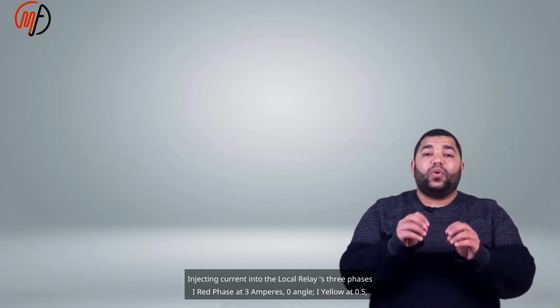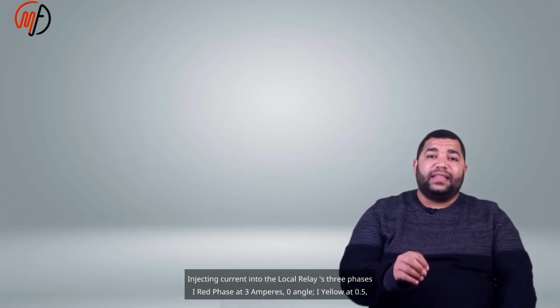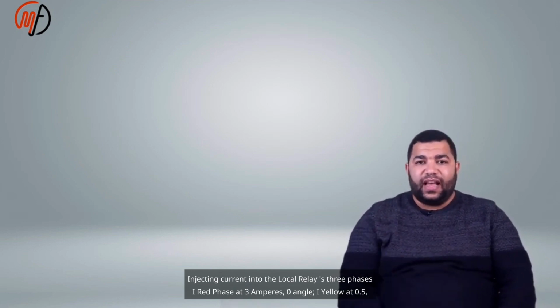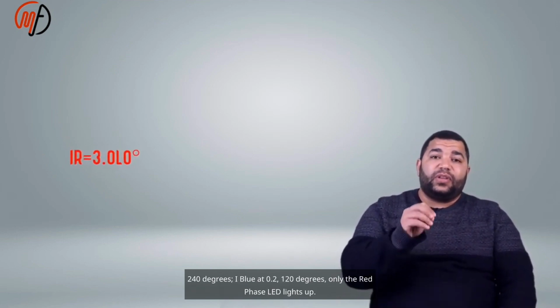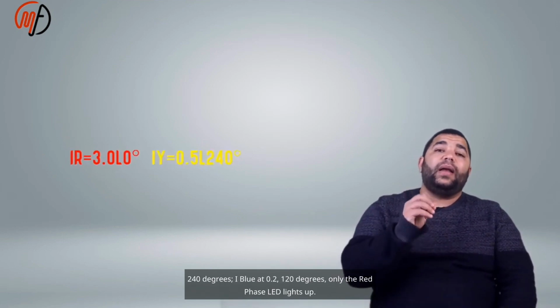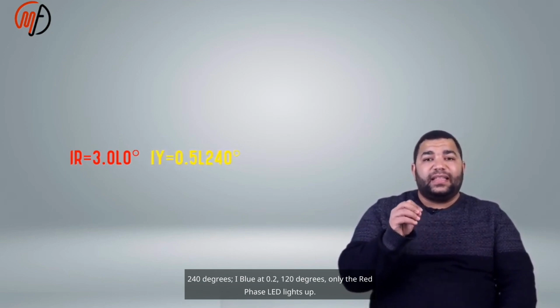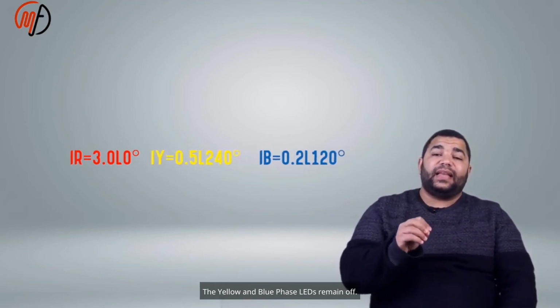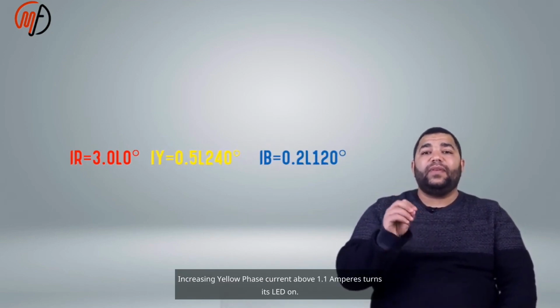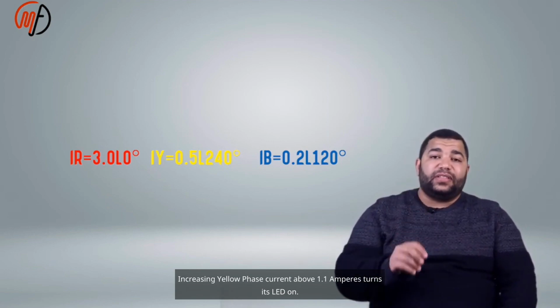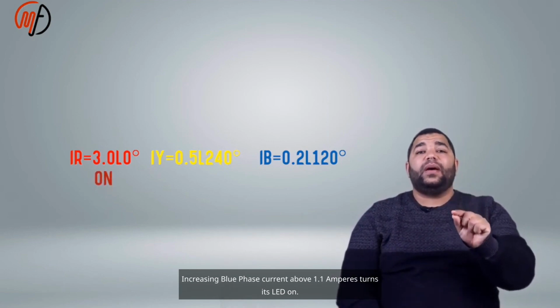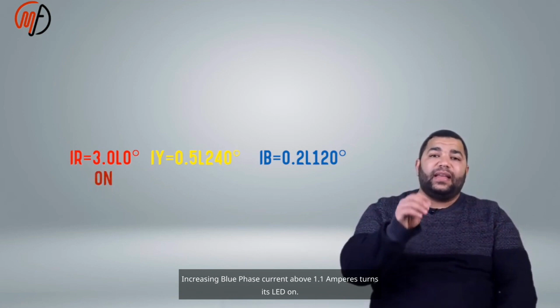Injecting current into the local relay's 3 phases: I red phase at 3 amperes, 0 angle; I yellow at 0.5, 240 degrees; I blue at 0.2, 120 degrees. Only the red phase LED lights up. The yellow and blue phase LEDs remain off. Increasing the yellow phase current above 1.1 amperes turns its LED on. Increasing the blue phase current above 1.1 amperes turns its LED on.